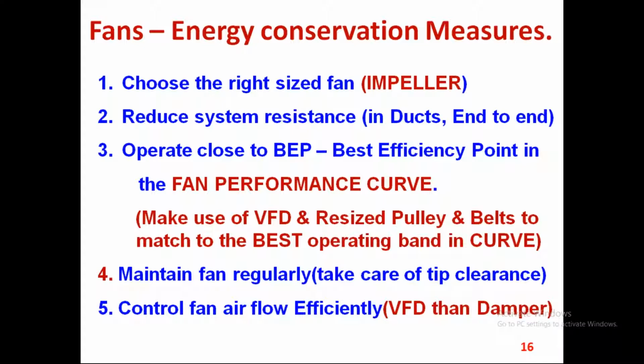Then reducing the system resistance. In many of the textile mills, instead of the T&D losses, which I was telling in the previous session, the transmission and distribution losses, whatever is generated in the air conditioning humidification plant is not delivered at the end point because the duct loss is more. Many of the air conditioning humidification plant vendors just improved the ducts. Instead of an ordinary GI duct, they have gone for an FRP duct, that too a circular type of duct at a bigger duct size. Automatically the system resistance dropped from end to end, and this also improved the total system efficiency.